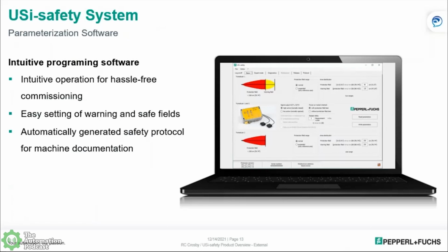So if you say, okay, well, I want the warning field to be set at 1.5 meters and the protective field to start at 1 meter, you can just type those figures in centimeters. So, 100 centimeters and 150 centimeters respectively. Or you can just use what the device sees and use that for commissioning as well. Like I said before, once you release the software, the sensor to the application, you've set your parameters. Now you've released the application.